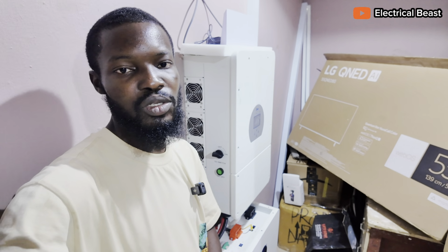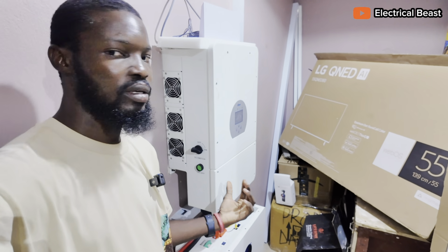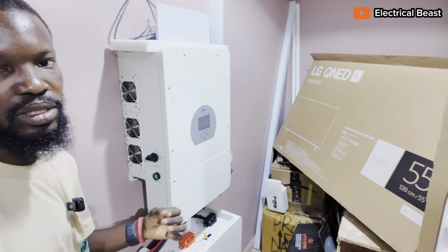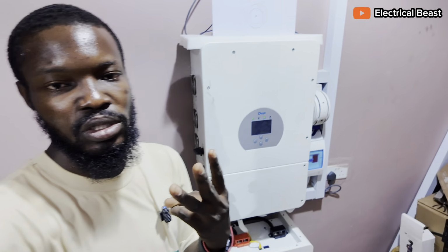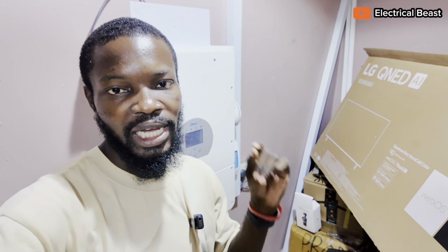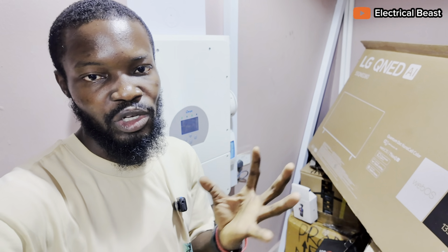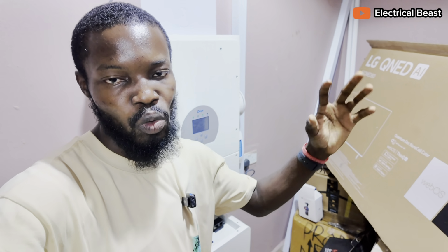We have about 9 panels connected in series to the first controller of this inverter, because this inverter has 3 controllers in total - 3 MPPT controllers and 6 trackers, 2 trackers per controller. We use only one side of the controller, one tracker, because we connected all 9 panels on one side of the roof.